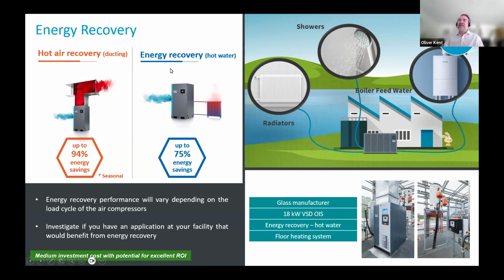Another way of recovering the heat of compression is to convert that heat into hot water. You can fit your compressor, or retrofit it, with options that will convert the heat of compression into hot water. Typically, that hot water will be coming off at 80 to 90 degrees C. That's good quality heat, and there are a lot of uses in industrial processes for it. We've got some examples here. You could use it in a central heating system to help top it up. If you have shower facilities, you could potentially use heat exchangers, using that energy as an assist to heat up your hot water.